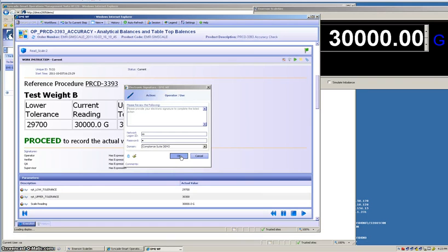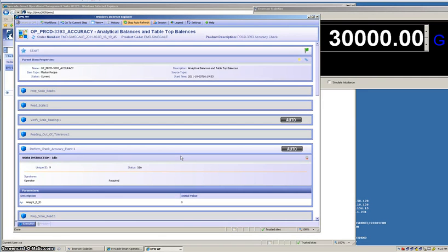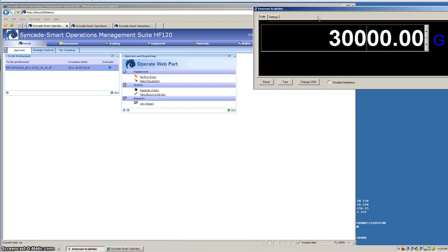As you can see today, we guided the operator through the procedure, ensuring that they had the correct information. We automatically interfaced to scales so that they didn't have to transcribe any information. When there was an error, we repeated it in a controlled fashion, reminding them to do a calibration in order to correct the problem. As you can see, using electronic workbooks and electronic logbooks really facilitates managing the equipment in your facility and eliminates a lot of problems caused by paper.